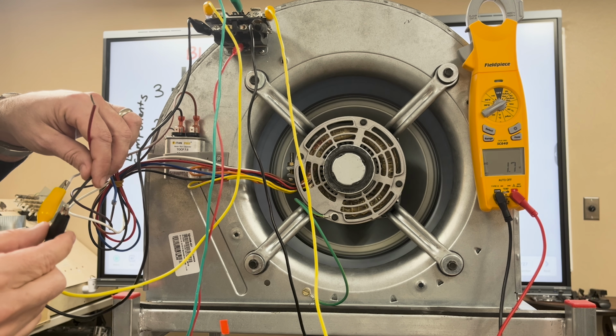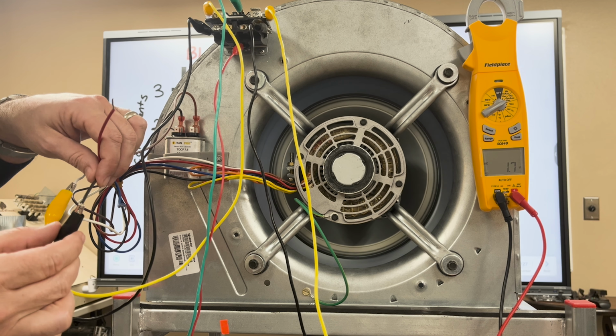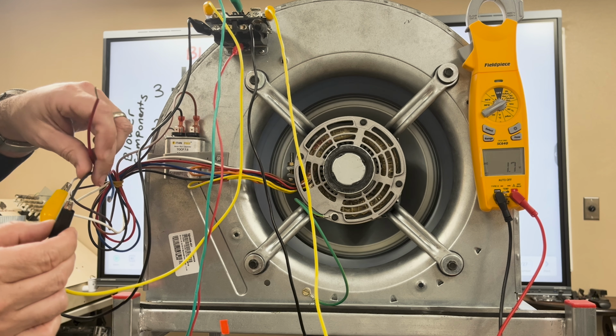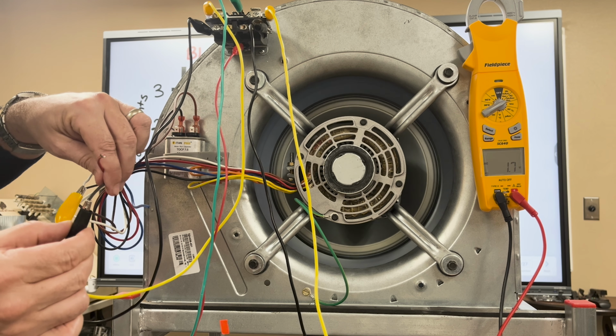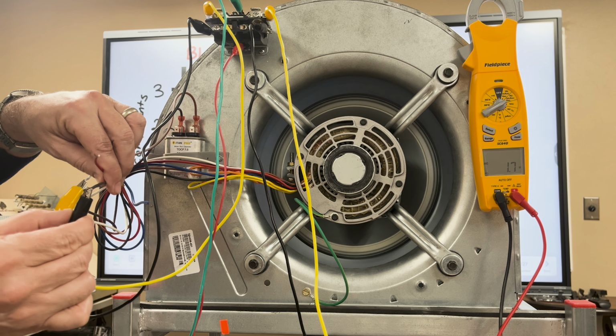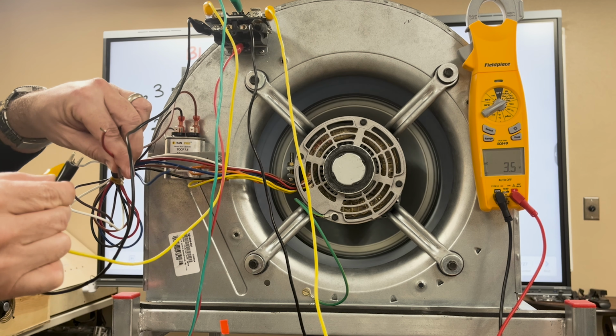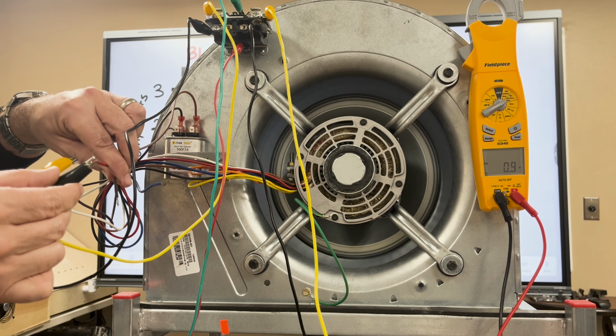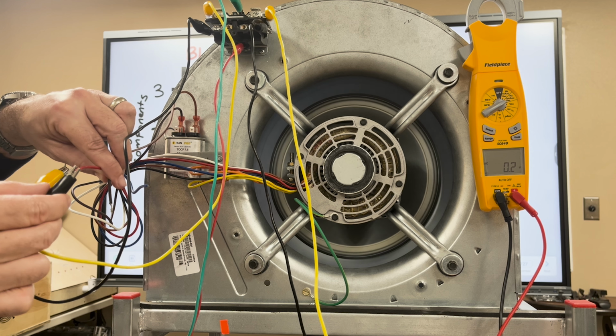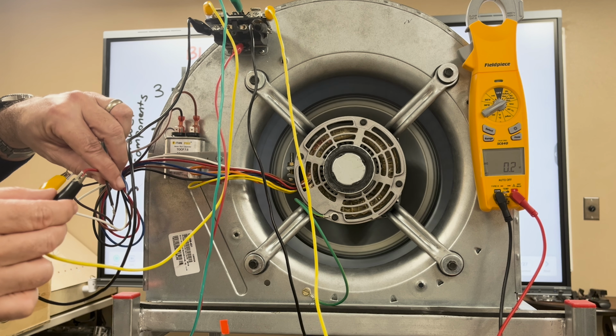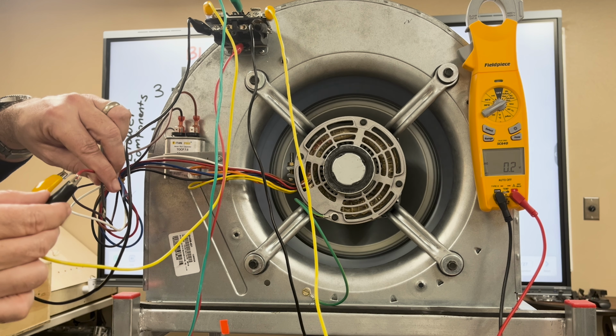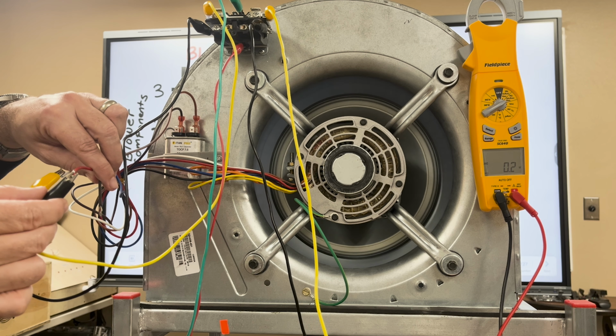There we go. If I were to cycle through different speeds, you'll notice the difference in acoustics on your end. You can't tell by volume of air on my end, it's blowing harder. We can't run all these speeds at one time because they're different windings, so there's different resistance on each one.